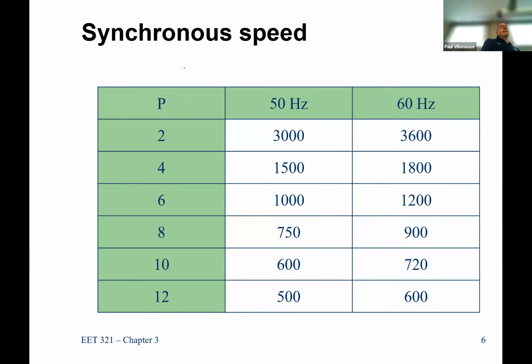So here's where we can build our table. We have P, the number of poles, and you'll notice there's never an odd number, because you can't have a north without a south and vice versa. In 50 hertz land, like Europe, a 2-pole machine runs at the equivalent of 3000 RPM. That's the synchronous speed — we'll get into the difference between mechanical speed and synchronous speed shortly. But that magnetic field in a 2-pole machine always spins at 3000 RPM.